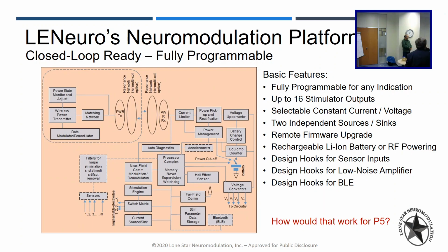I'm pretty sure you comply with 60601, but in terms of software, this has been designed completely for the standards. The primary one is 60601-1 and also -2-16, 14971 for safety, 14708 for implantable devices, 62304 software lifecycle management. What about the battery? Is it UL 1642 compliant, or is it just full compliance to the 606?